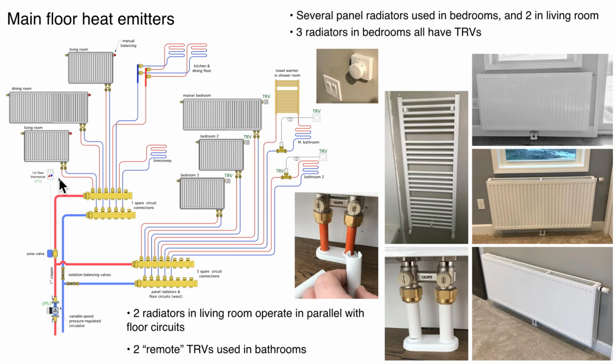Yeah, and going back to this system, we're running a maximum water temperature here of 110 Fahrenheit, and we're at about 12 psi. So from a temperature and pressure standpoint, we're well below those limits that Lance talked about on the tubing. I want to make one last point before I leave this slide.